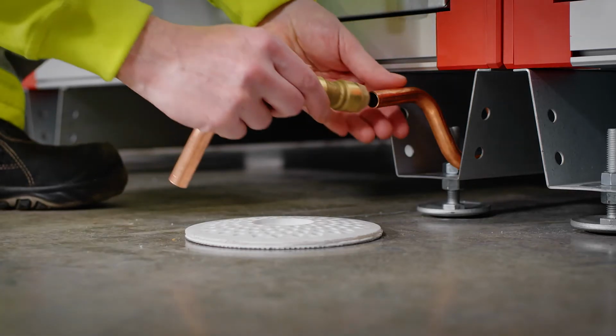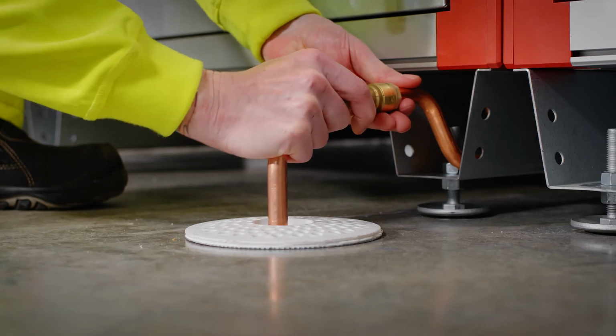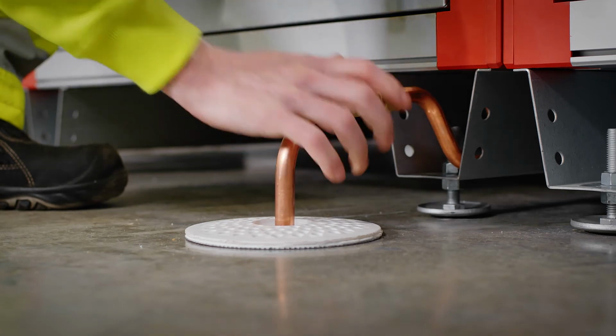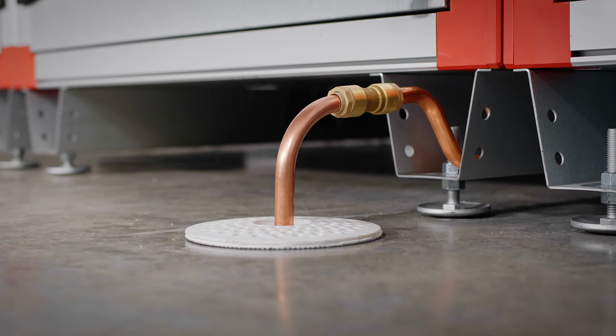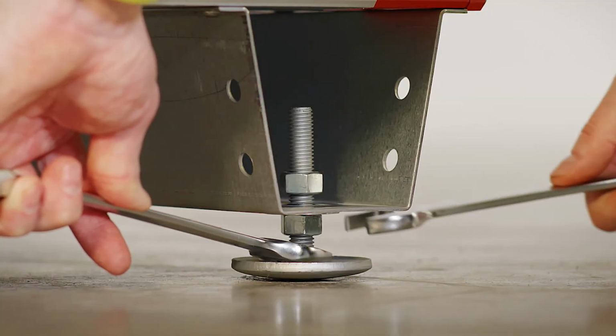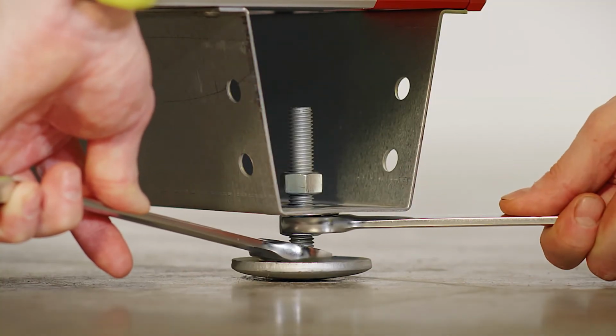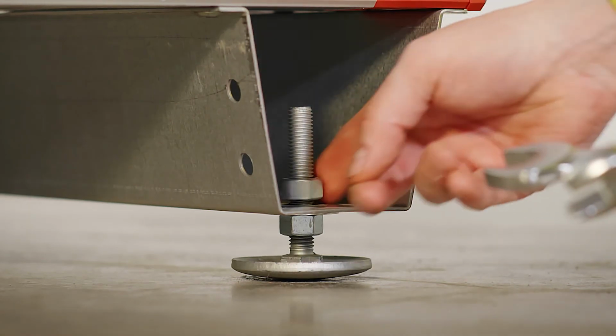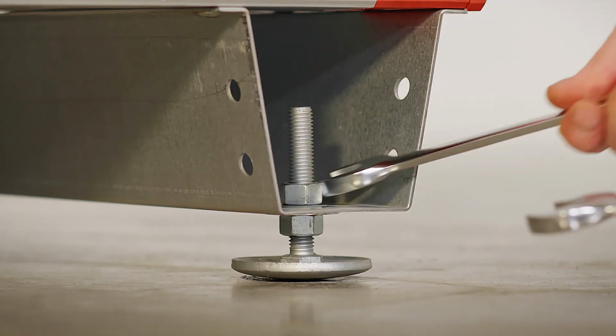The drainage on the cooling unit is then connected via a water trap to a floor drain. Remember to check that the doors can be opened and closed properly. If not, adjust the front feet so that the doors are perpendicular.